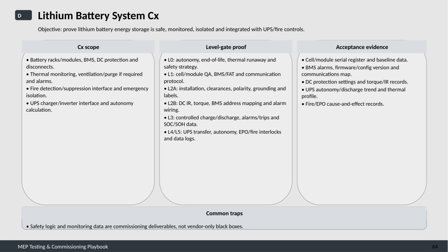First, the scope of commissioning includes key components such as battery racks and modules, the battery management system or BMS, DC protection devices, and disconnects. It also involves thermal monitoring to prevent overheating, ventilation, or purging if needed, and alarm systems for early warnings. Importantly, the system must interface properly with fire detection and suppression mechanisms, including emergency isolation protocols. Additionally, the UPS charger and inverter integration is tested, along with calculations to confirm the system's autonomy. Commissioning is performed in several level gates.